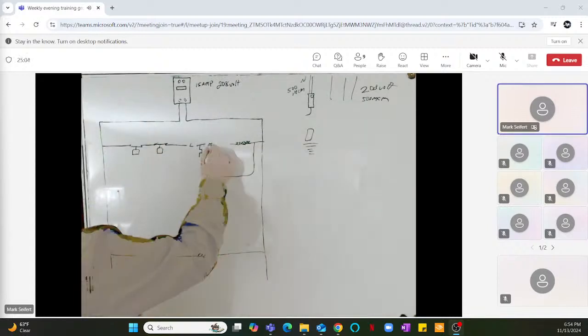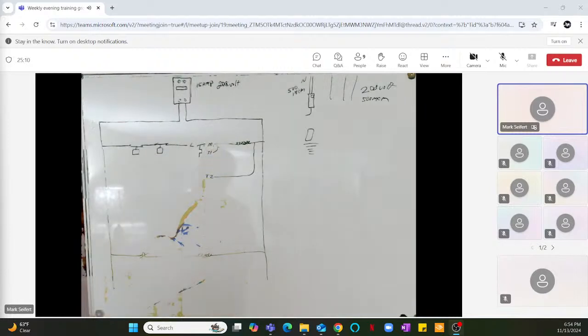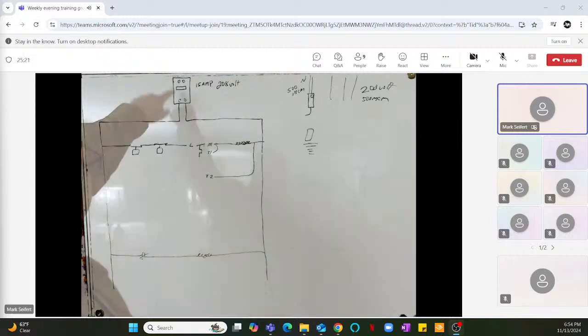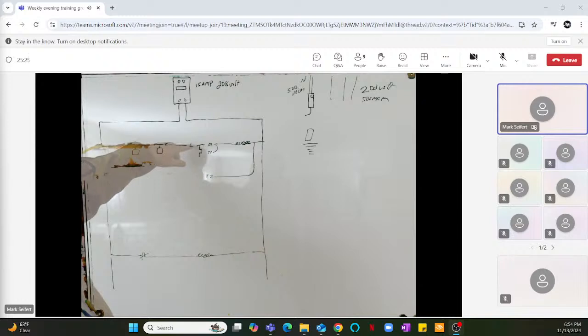So let's put our jumper, and then M connects to our coil. So when everything is working good, we get our 208, 15 amp, 208 volt circuit, goes down this way, comes through the controls, hits the L, the control is closed, hits the M, compressor contactor comes on. Normal operation, right?